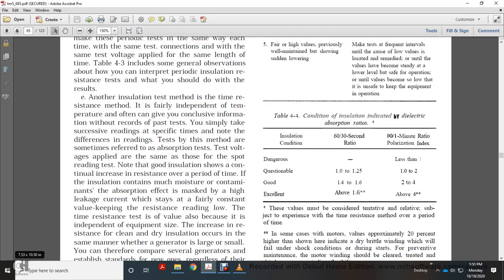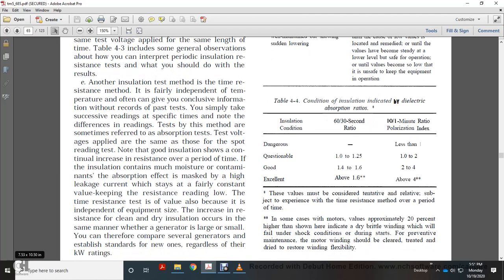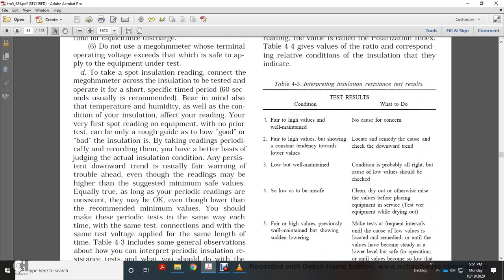Note that good insulation shows a continual increase of resistance over a period of time. Insulation contaminated with moisture has the absorption effect masked by a high leakage current at a steady, nearly constant value, keeping the resistance reading low. Time resistance testing is also independent of equipment size, and the resistance increases as cleaning and drying of insulation occurs. The same holds for generators, large and small. You can therefore compare several generators and establish standards for new ones regardless of their kilowatt rating. And then you have your tables.